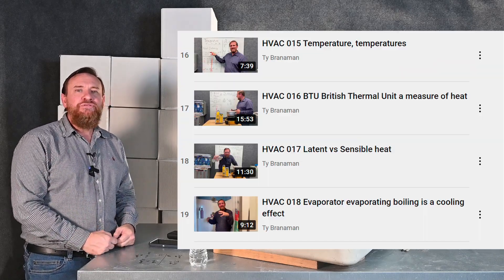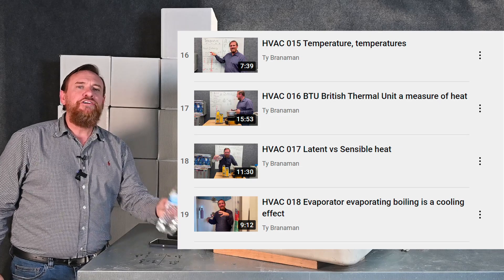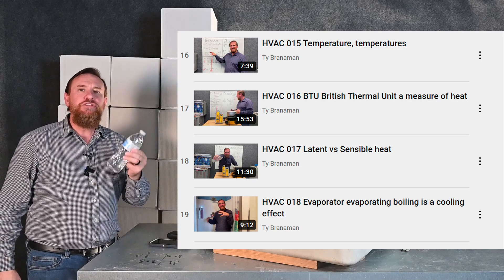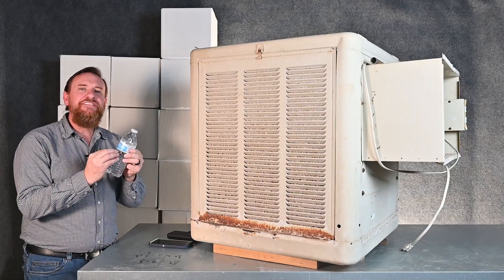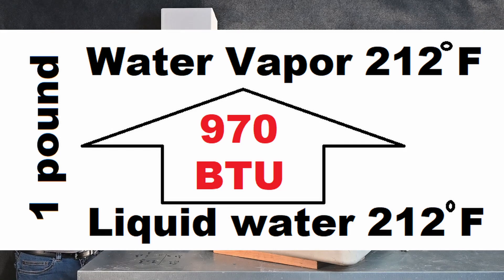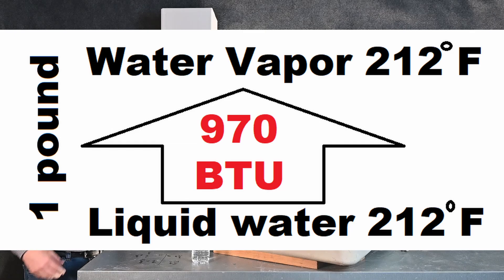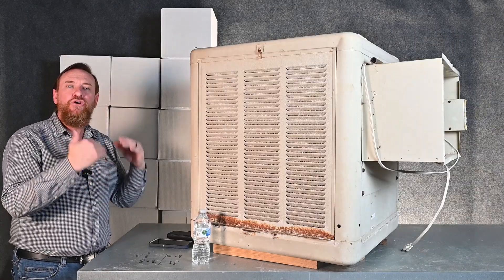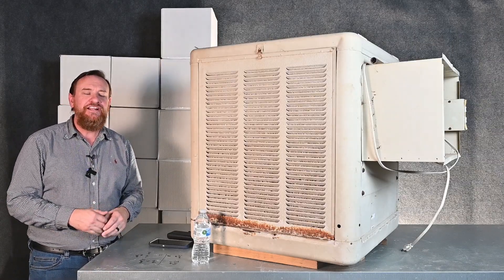If you remember earlier, we talked about BTUs as heat energy. Changing water from a liquid to a vapor — from 212-degree liquid to 212-degree vapor — took 970 BTUs of energy to make it change state. That water changing state kept it at a cool 212 degrees Fahrenheit.